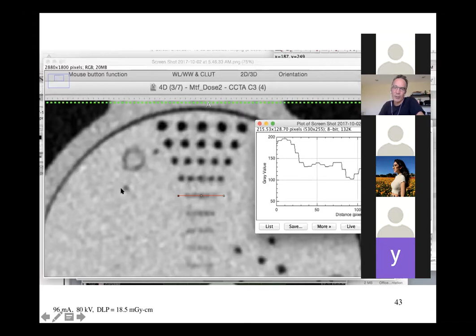And as a definition of resolution, if we can image a dot that is much smaller than the voxel, or the inherent resolution of the system, when we image that dot, what we see usually is a blob that looks something like this in our image. It isn't a dot that is this big, because the image is not capable of making something that small. It gives us this blob. This is basically another way of characterizing the spatial resolution of the system.